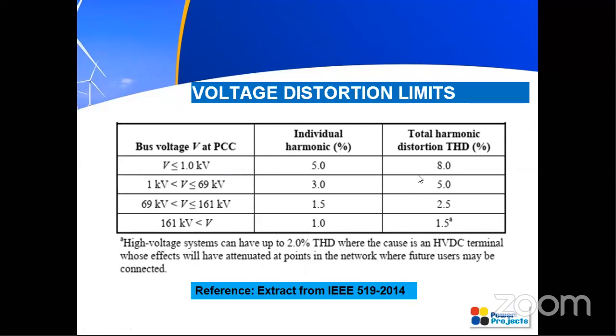So these are the voltage distortion limits given in IEEE 519 2014. They are saying that you have to check the bus voltage at the PCC. If it is less than 1 kV, that is for low voltage distribution systems, usually we will be employing the range of 4 and 5. For that, the individual harmonic should not exceed 5% and the total harmonic distortion should not exceed 8%. I hope everyone knows what is individual harmonic and total harmonic.